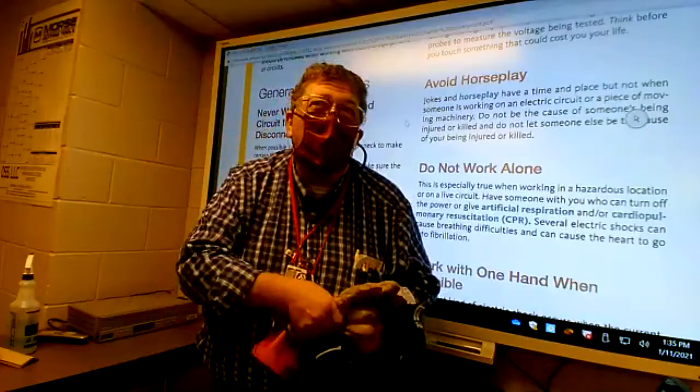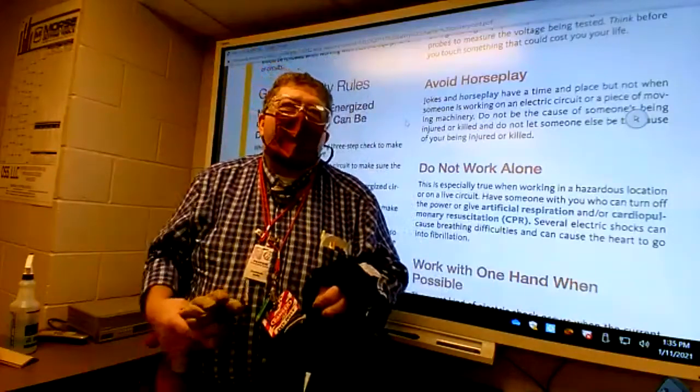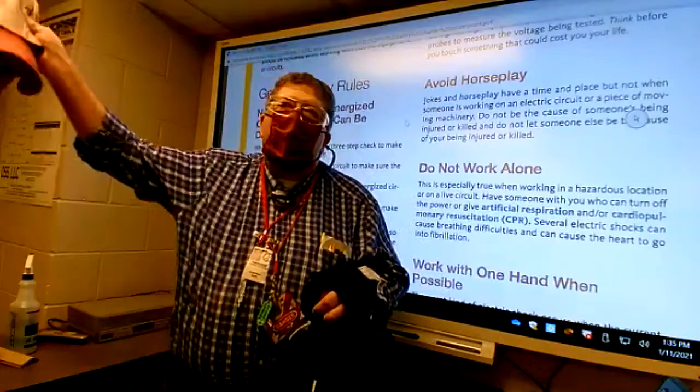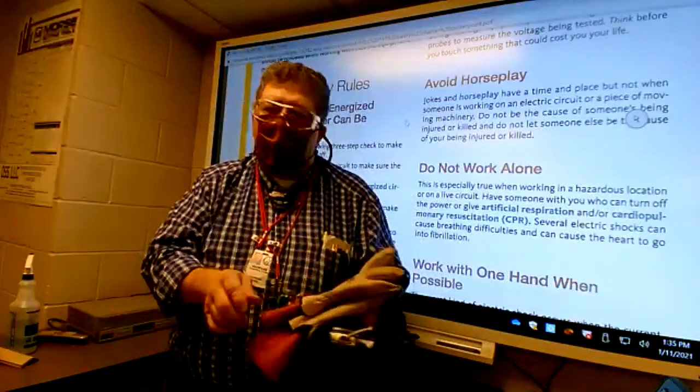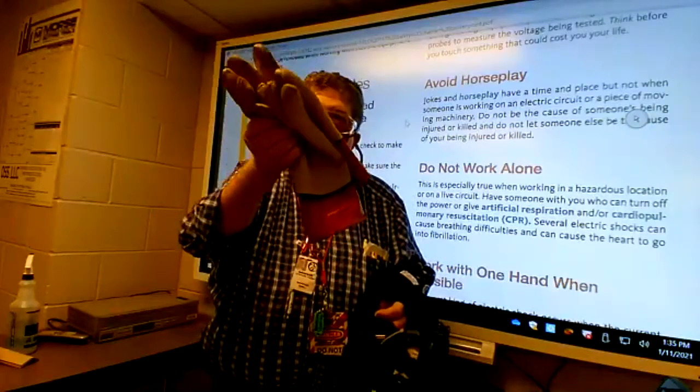They're contaminated. You get one pinhole, you got to throw them away. They're no good, because you could get killed off of it. I've heard of cases, the worst, people with the power company, somebody got electrocuted and died because of a pinhole in a glove. So again, protect these.